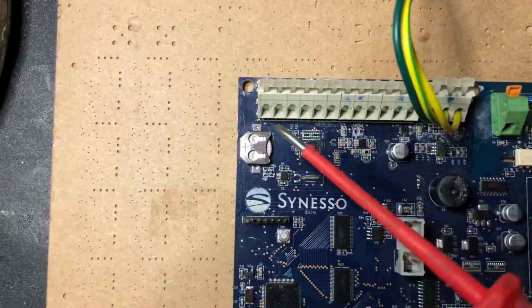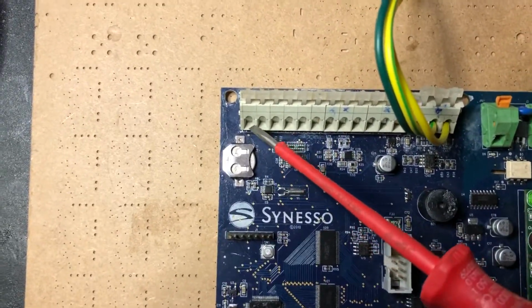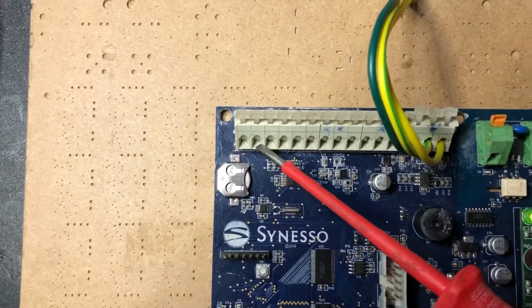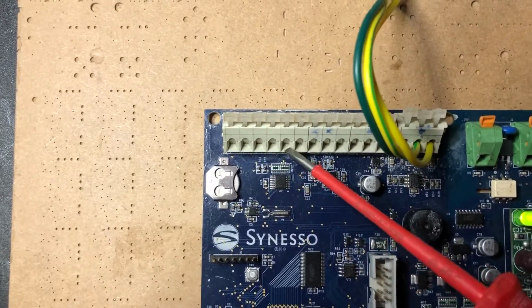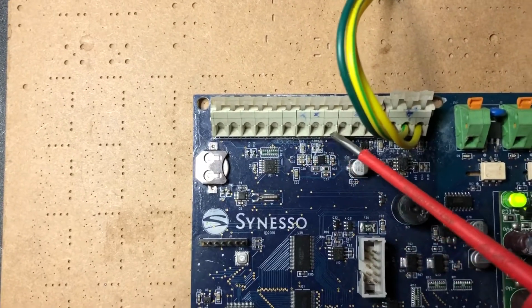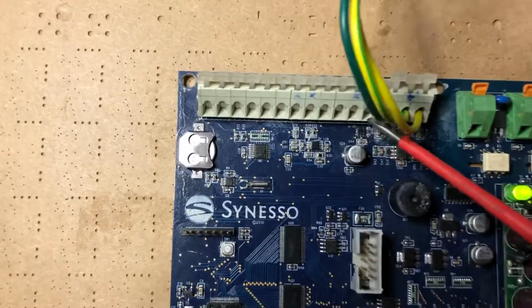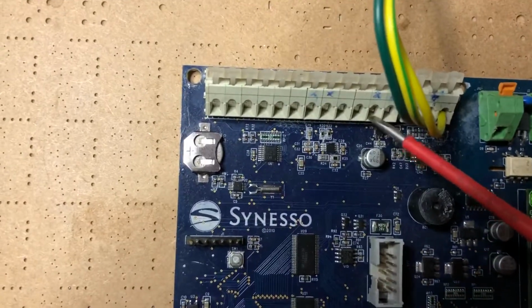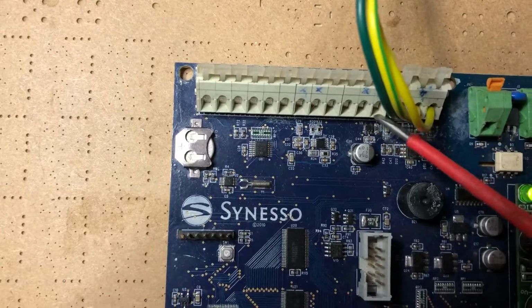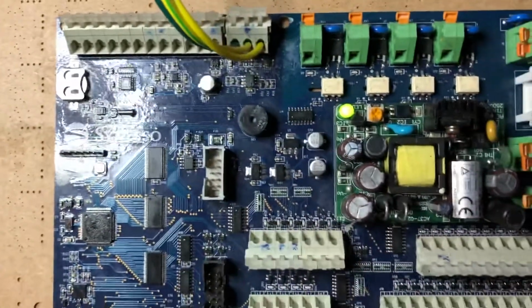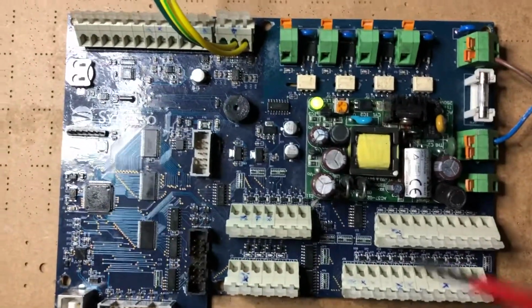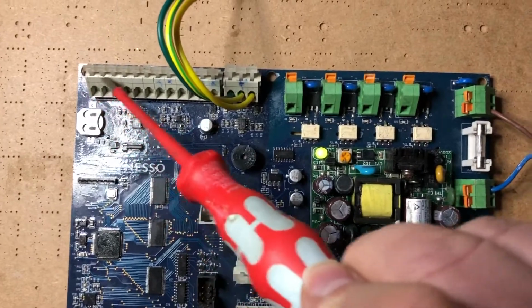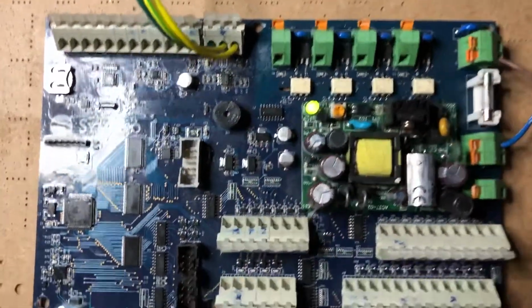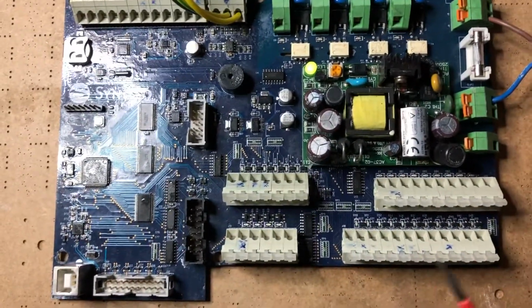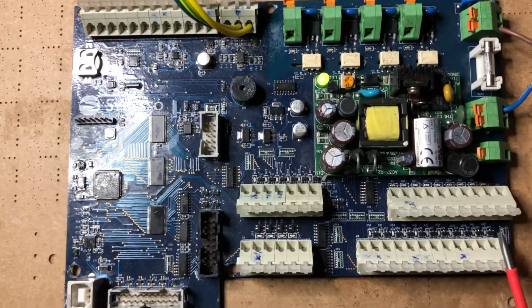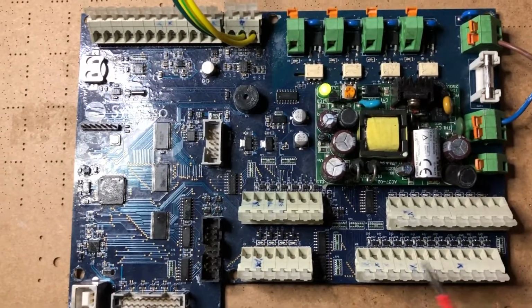Now up here are your NTC thermistors. Group 1, they're in pairs. First pair is group 1, group 2, group 3, group 4, steam. I don't know if I ever knew what the 6th pair is for. If anybody knows, drop a comment below. But that's the exception, left to right. Now when we move down here, we've got the solenoid valve outputs, and these are right to left.